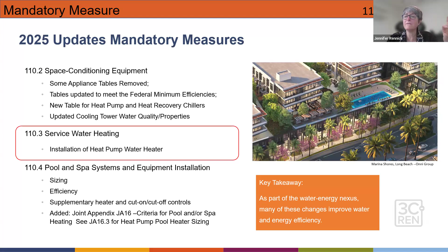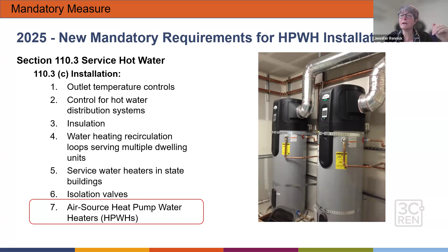This section for service water heating has always included temperature controls, hot water distribution system, insulation, etc., but now they've added item 7, specifically air source heat pump water heaters, or HPWH as you'll see it in the code. Some of this was recommended guidelines, and a lot of this information you might have seen in the prescriptive part of the code, but now it's moved to a mandatory measure.